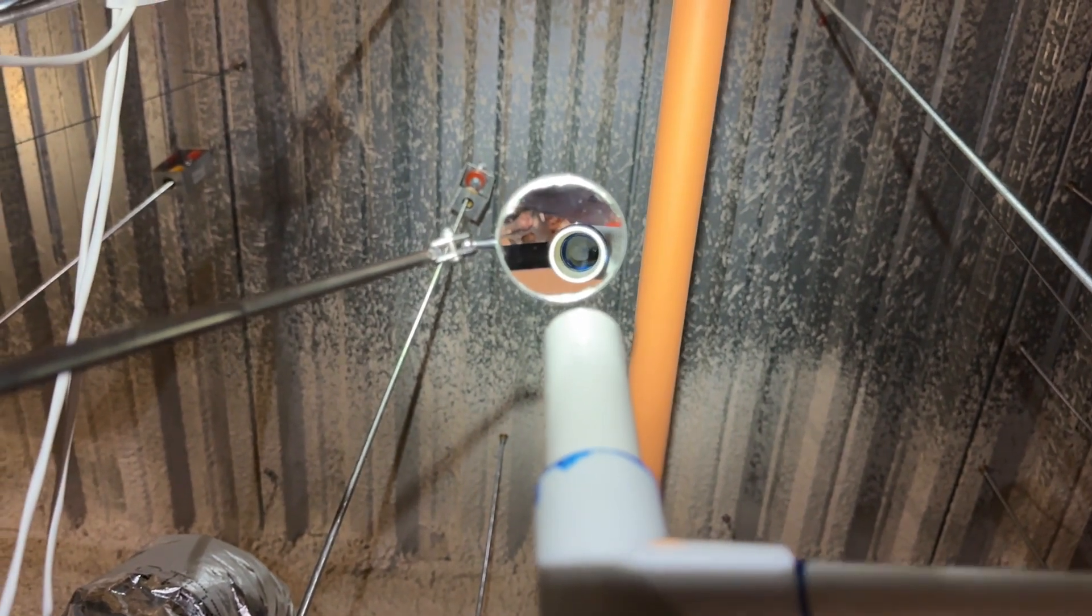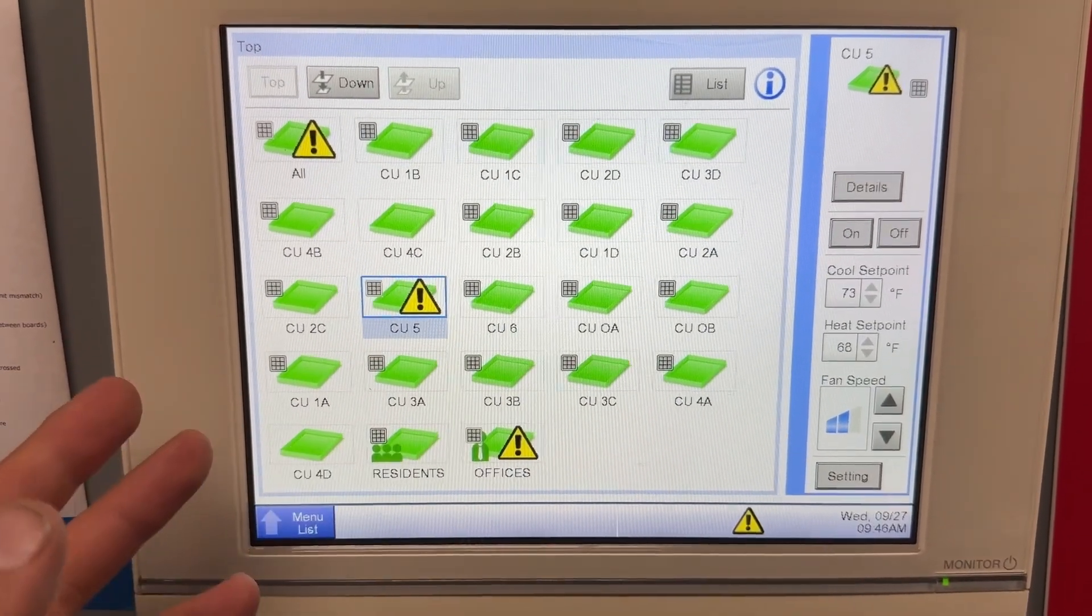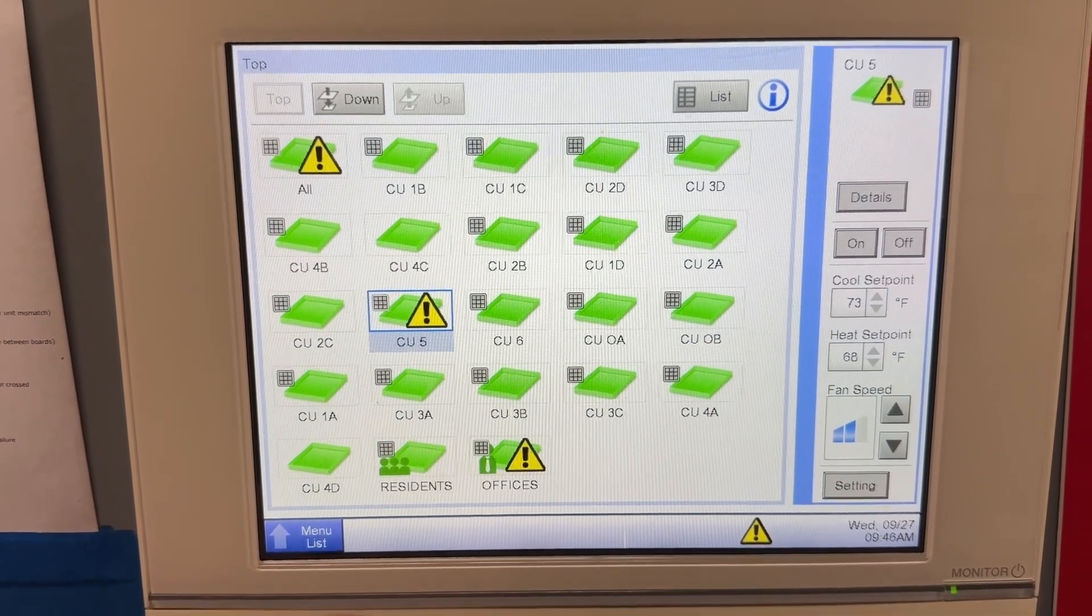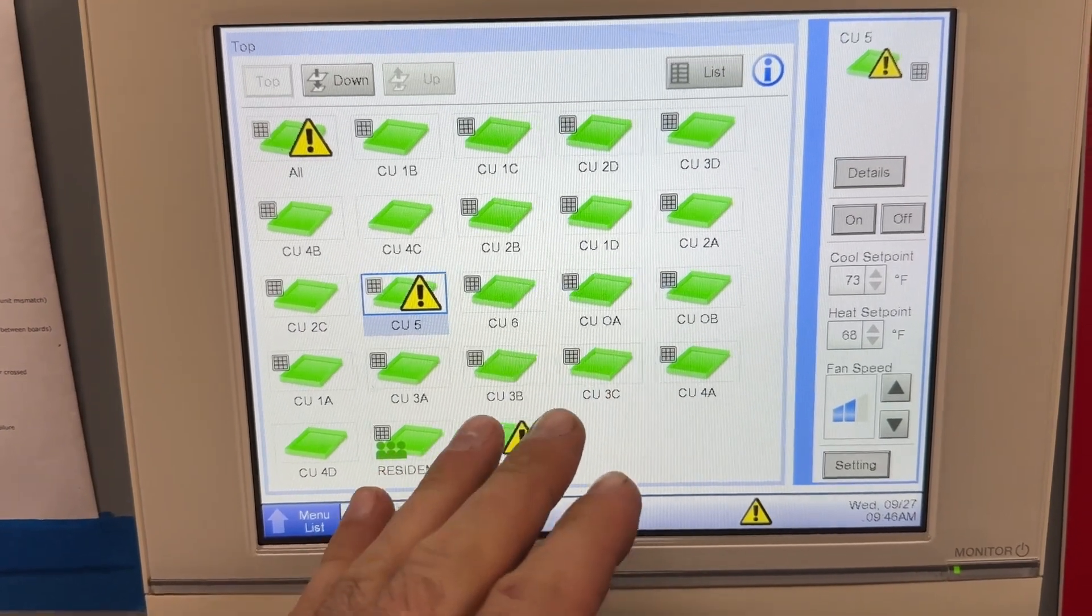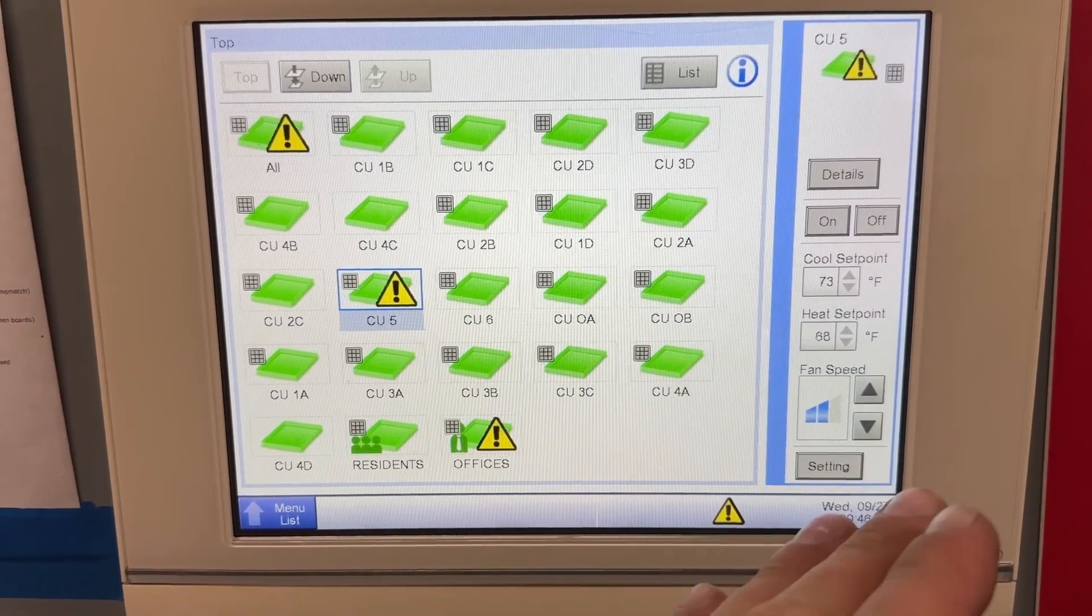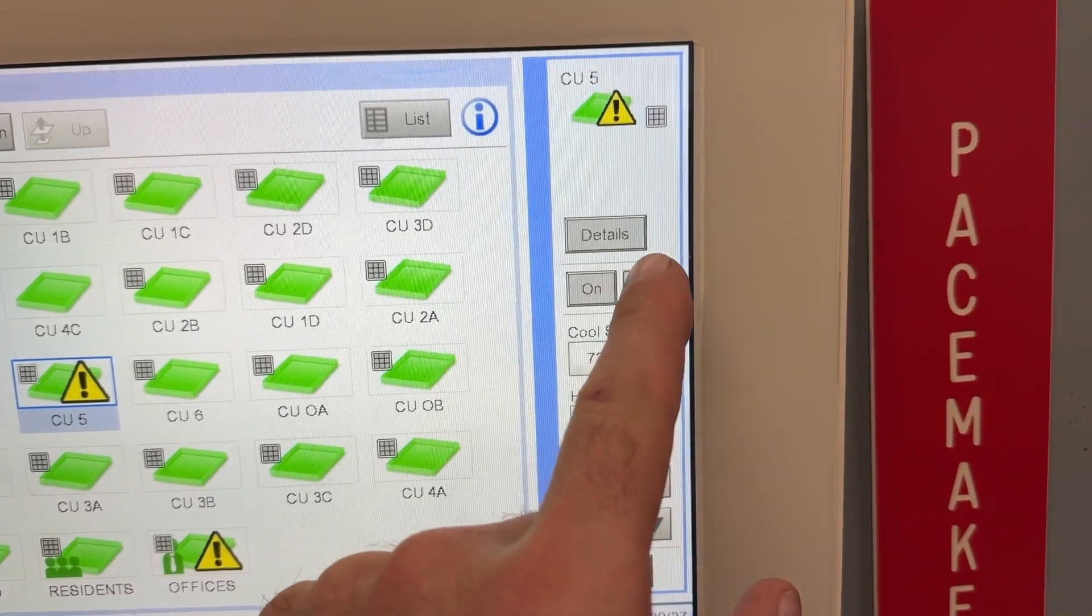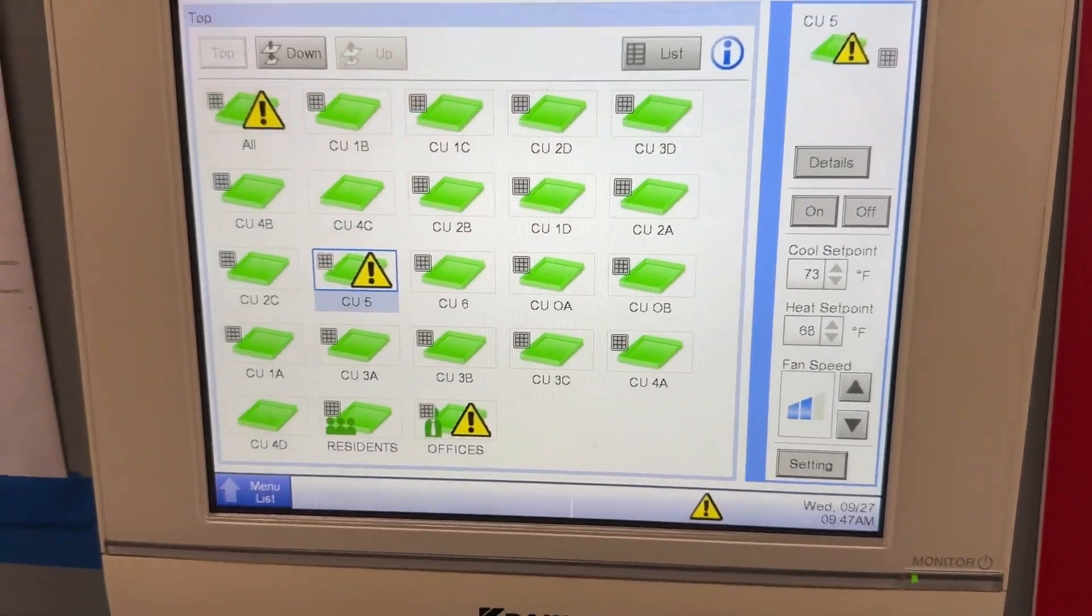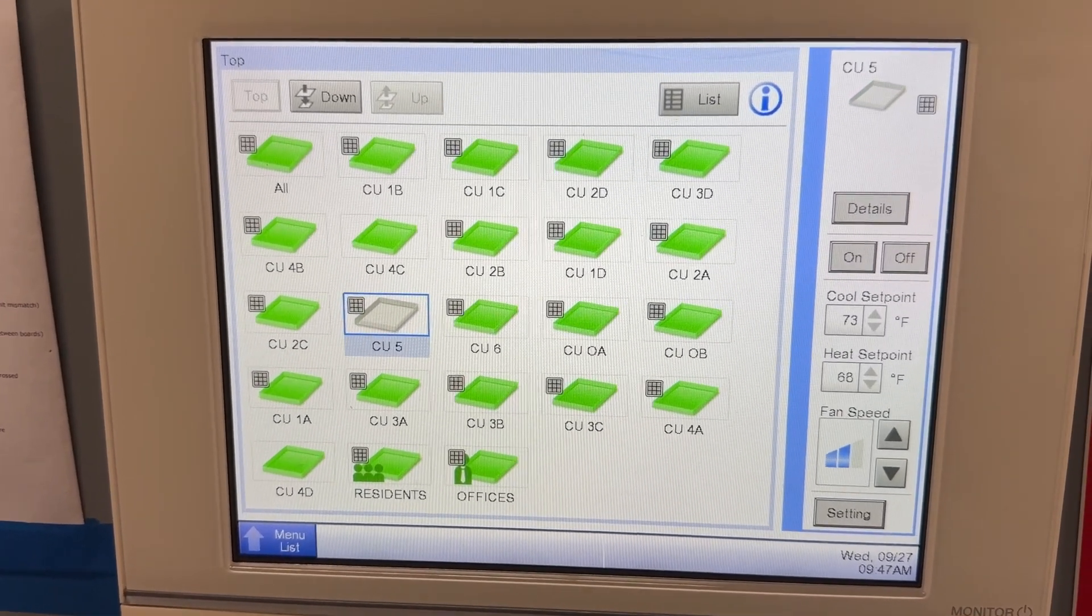Maybe this pump does have an uplift. Let's look at something real quick. What I'm wondering is if this system gets cut off or switches over into heat and that condensate pump shuts off all that water drains back and activates that switch and then you know if it stays active for long enough it'll throw the code and those pumps are very slow so even if you cut it off for a second and back on that could cause a code because that pump just can't move that amount of water that fast. So I'm just gonna cut it off and I want to see if that water drops back down into the pan. So let's see. Normally takes it a second. There we go.